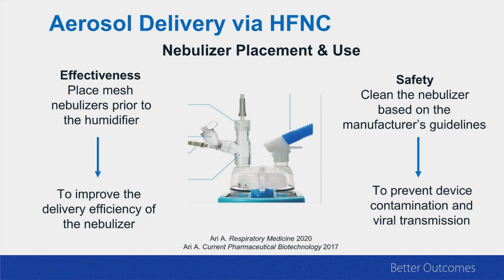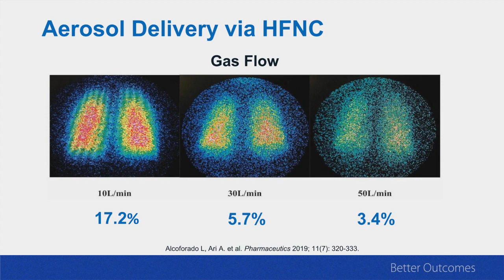What about gas flow? This is a study that we conducted with our colleagues in Brazil, in which we wanted to quantify aerosol drug delivery with the high flow nasal cannula at 10, 30, and 50 liters per minute. Lung dose at 10 liters per minute was 17.2%, as opposed to 5.7% at 30 liters per minute. When we increased the flow rate to 50 liters per minute, lung dose dropped to 3.4%, and that was a lot. So here's what I'm suggesting to you.